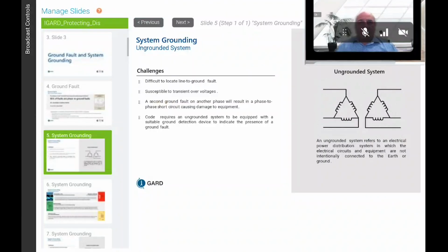So we're going to discuss a little bit of ungrounded systems. An ungrounded system has no intentional connection between the phase conductors and ground. It's very difficult to locate where a ground fault is. And we used to have a lot of these back in the 50s and early 60s. And now they're more strategically placed for certain applications. They're susceptible to transient overvoltages.